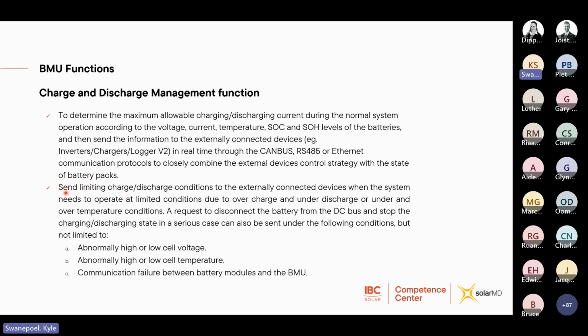Then the limiting information. So this is very important when it comes to a charge and discharge cycle. So sending limiting charge information to the inverter when the battery is full, to essentially throttle the charging, to stop it from charging the battery so that it doesn't overcharge. And this is the same for a discharge condition, to not under discharge the battery. So SolarMD works really closely with the various inverter brands to build those protocols for the inverters into the logic of the BMU, which allows this information to be conveyed to the inverter so that it will limit the charge and limit the discharge to essentially protect the battery.